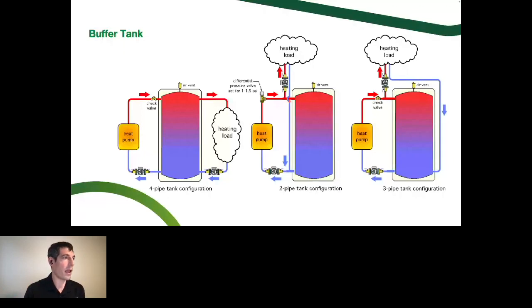Nothing's happening there. As this ECM circulator starts to slow down, some of the zones close, then we start to have some energy going out to the building direct to load still, but some of it's going to come back into the buffer tank and start to charge this up. So we'll charge up this battery, and then the heat pump may even turn off. And if there's just a little bit of energy going out to the building still, we can actually pull from the right to the left out to the system here. And we're actually just using the battery to power the building until this thermal battery runs out of energy. So that's a 2-pipe configuration.